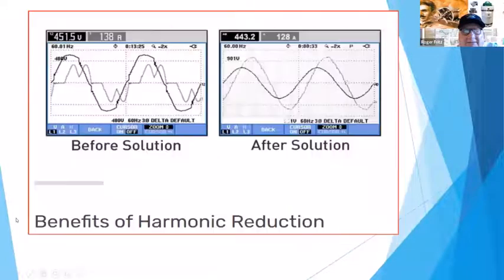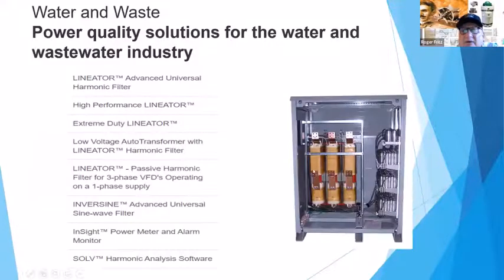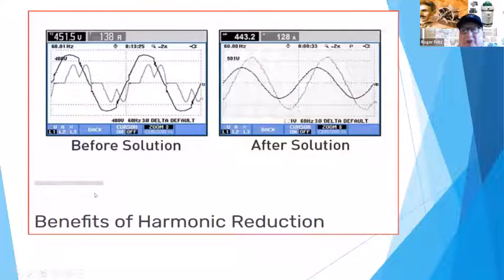because of the power losses. If you don't get that cleaned up, even on the output to the motor and the input, as well as possible, you're giving up efficiency, because this motor was pulling the same, but all you've got to do is do the math. 451.5 volts times 138 amps. I could do it in my head, but I'll do it on a calculator.